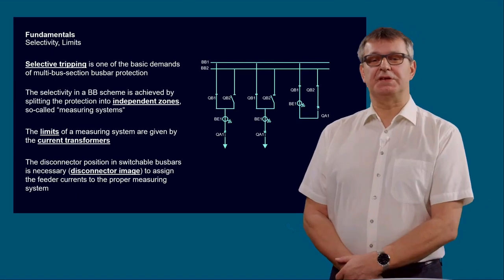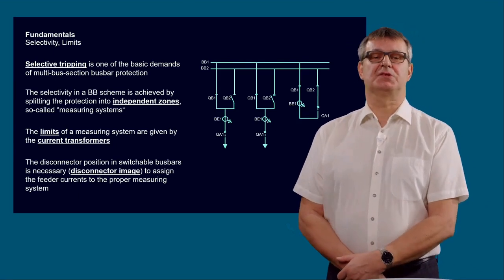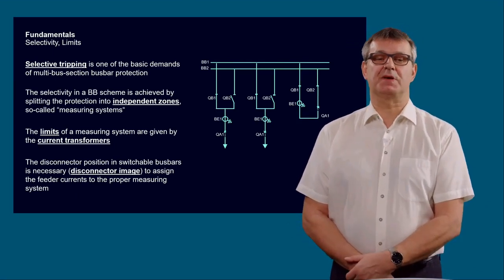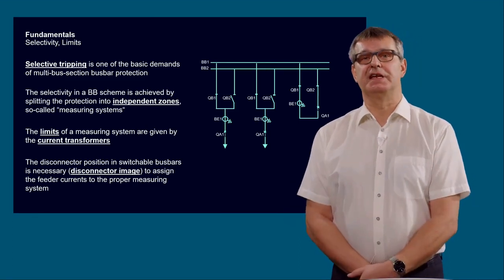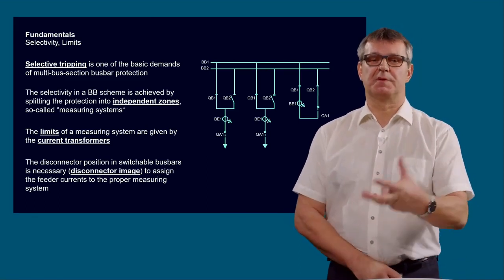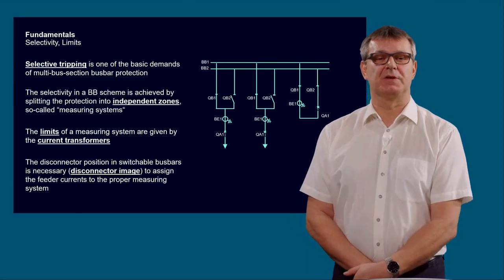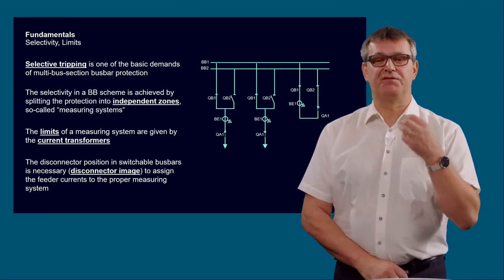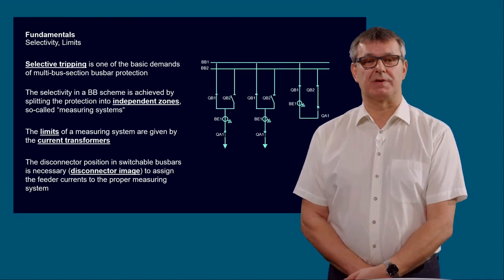And the disconnectors: we need disconnector positions in switchable busbars. It's different, of course, in a single busbar, but in a double busbar or triple busbar, we need the disconnector image to assign the feeder currents to the proper measurement systems.